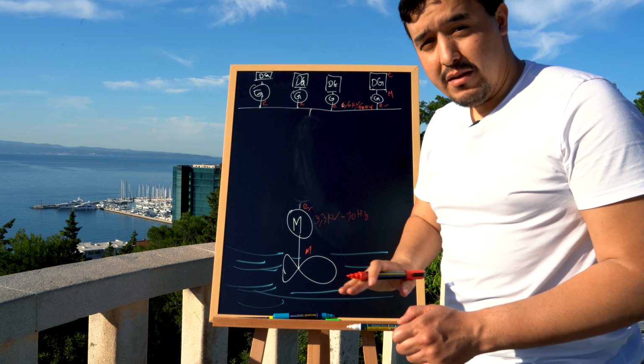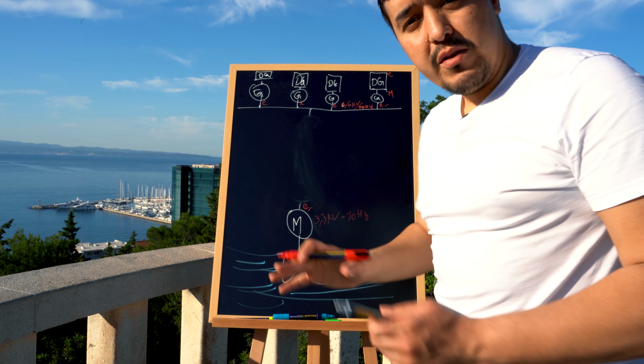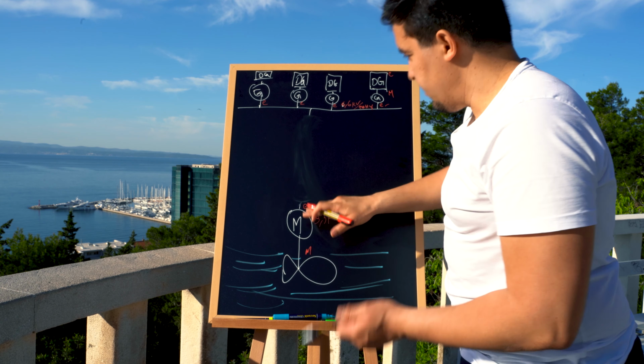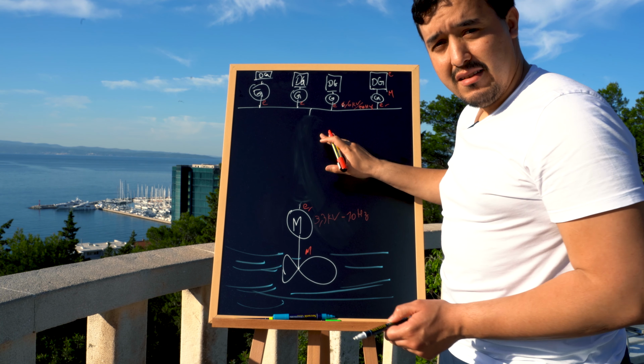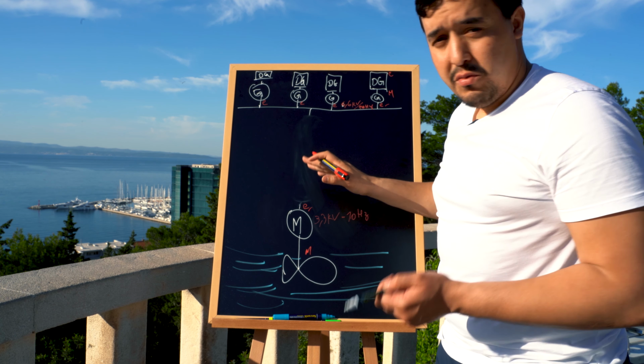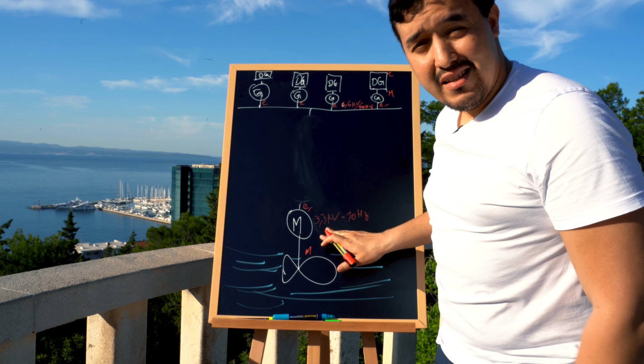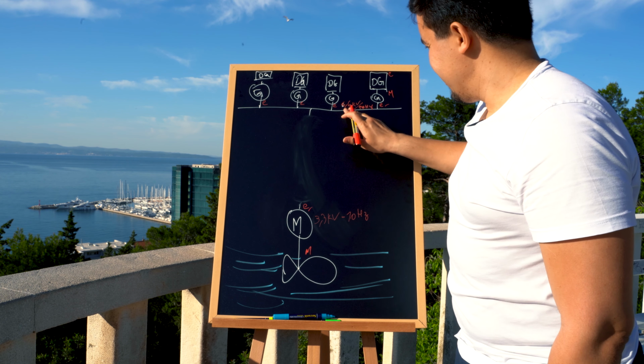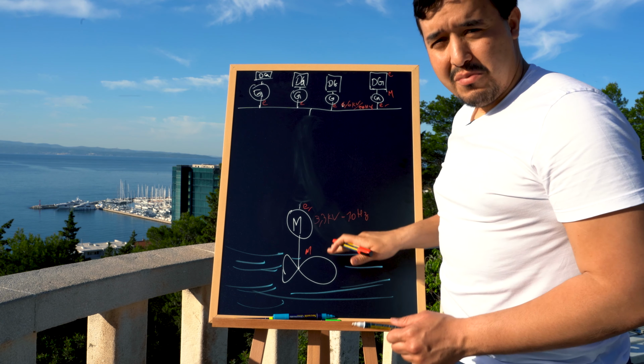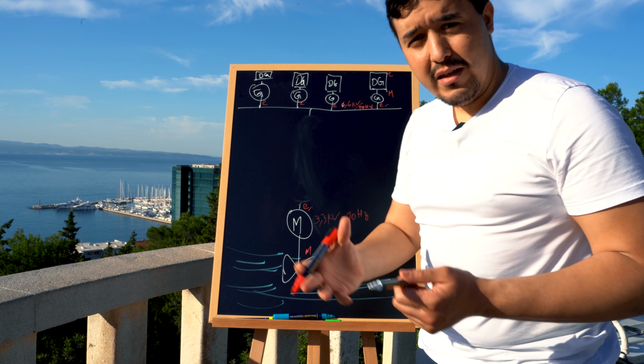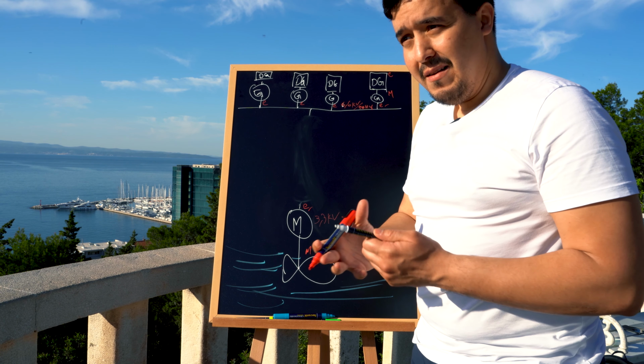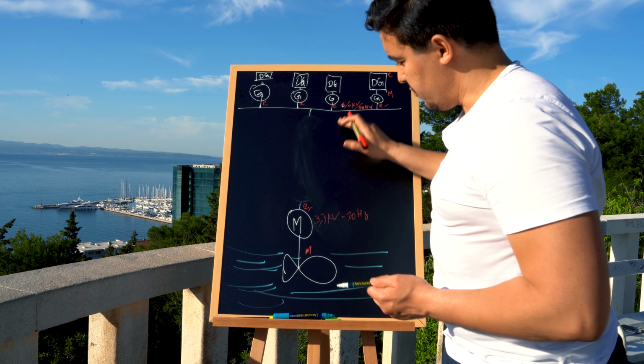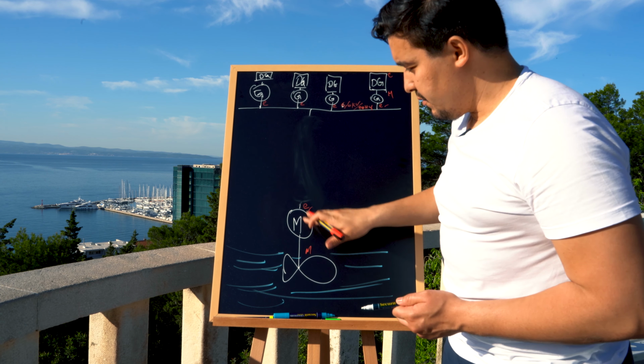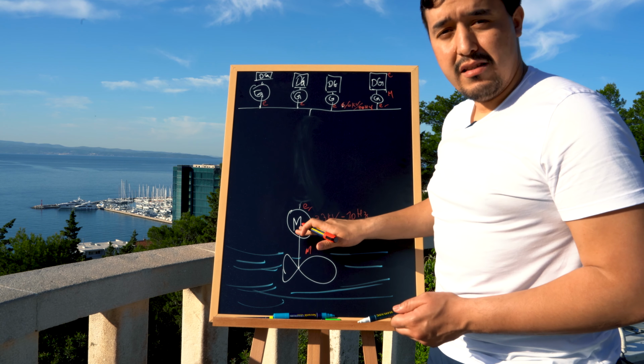So forget the problem of wanting to vary the speed of the motor. You simply cannot connect this to this. Well, you can do it, but it will not work, because if this machine has been designed for 3.3 and you connect it to 6.6, the first problem is the insulation of the winding of the machine.